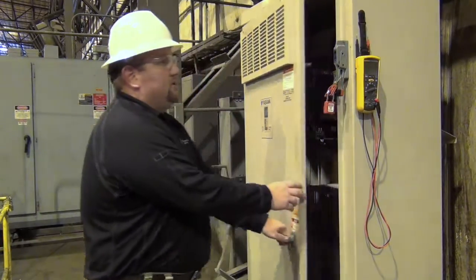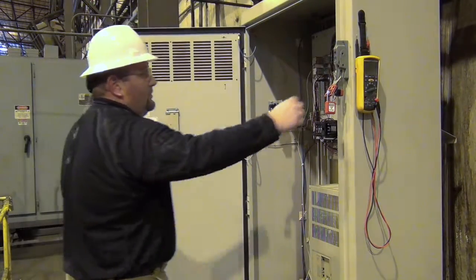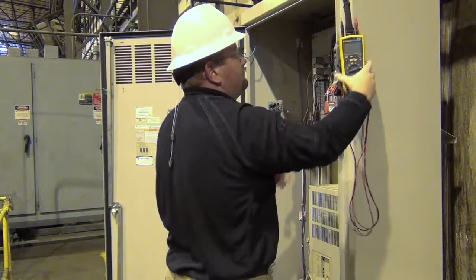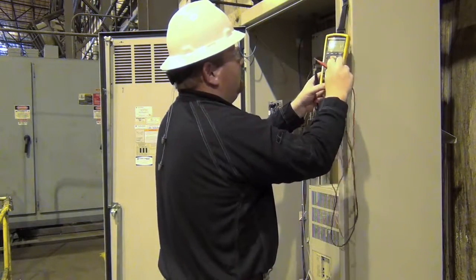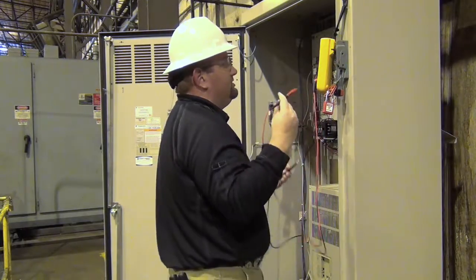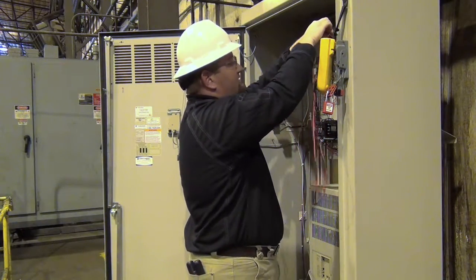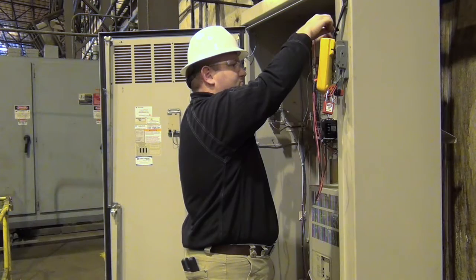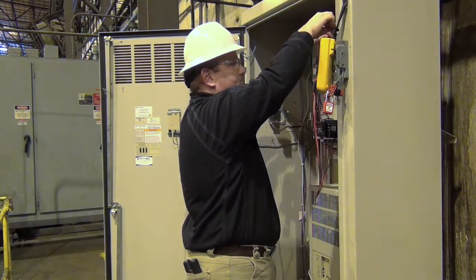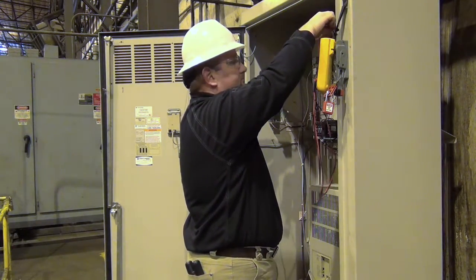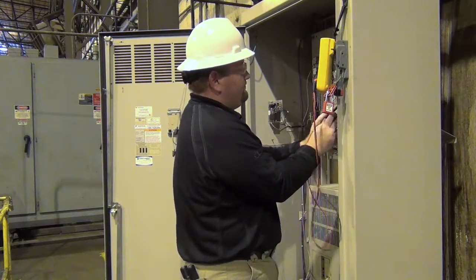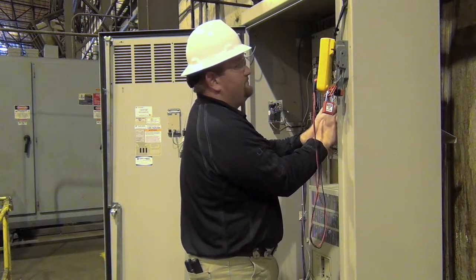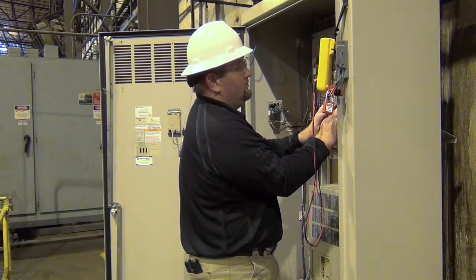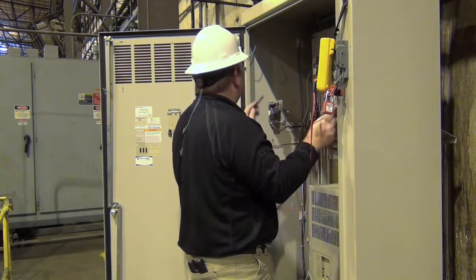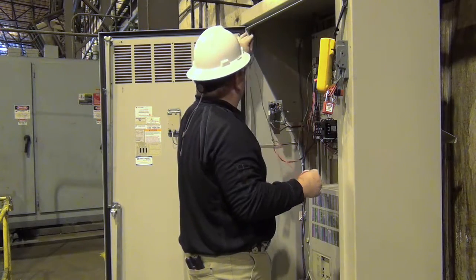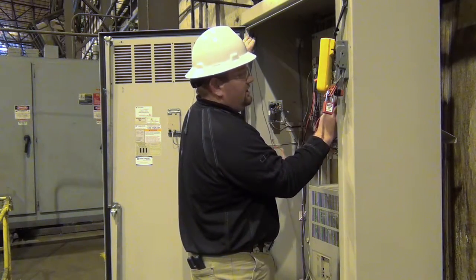So what we're going to do is go ahead and open the drive up, get our voltmeter, go on to AC voltage, and we'll just check our voltages. Okay. And at the bottom breaker, line to line, and we'll find the good ground, and also do a check on each line into ground.